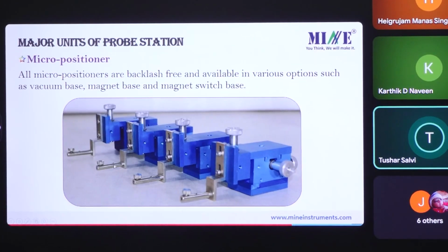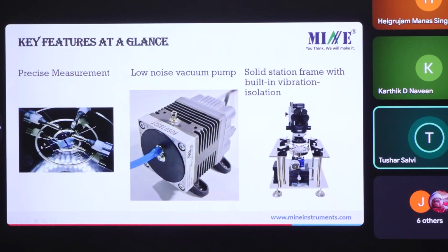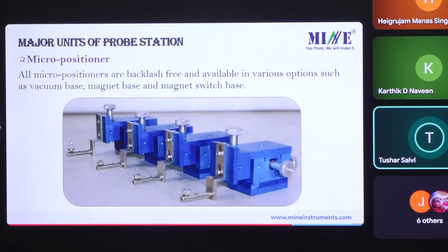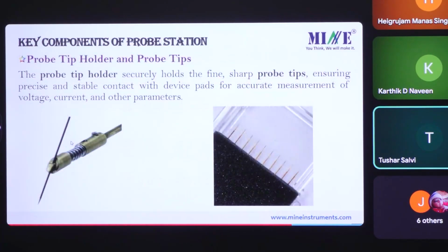Here you can see the tip holder where we can mount our tip, just by using this screw. After the head attachment, you will find this kind of total mechanical assembly, where you can tip and probe your wafer. According to user needs, I will show you in the last. This is our tip.